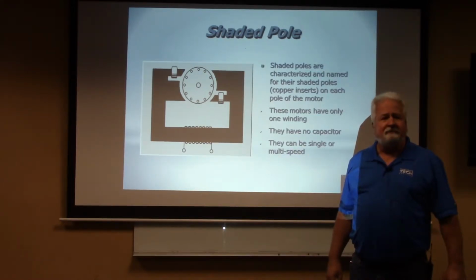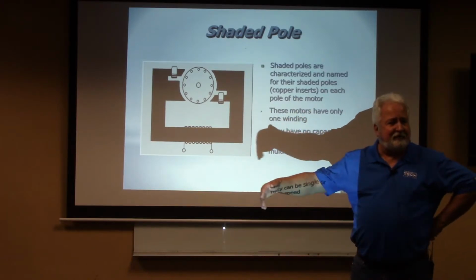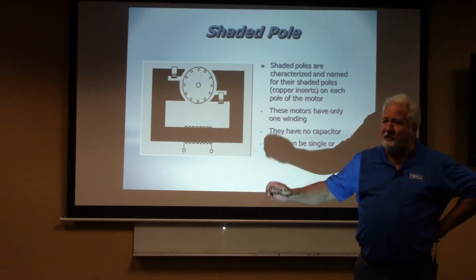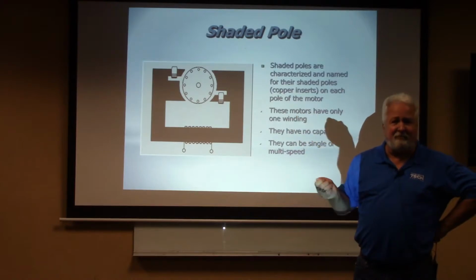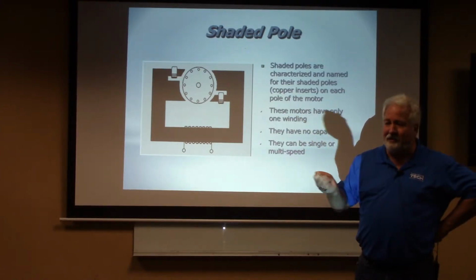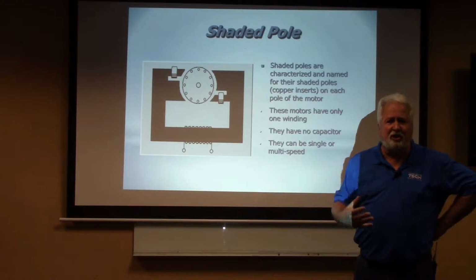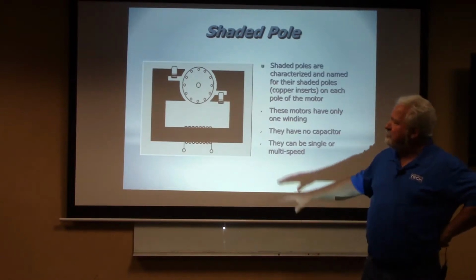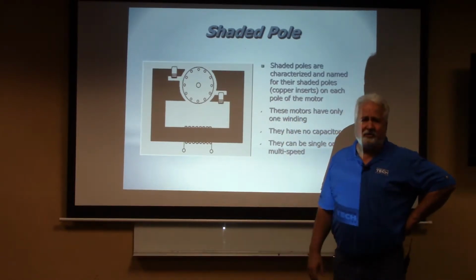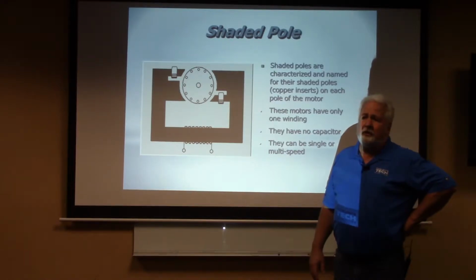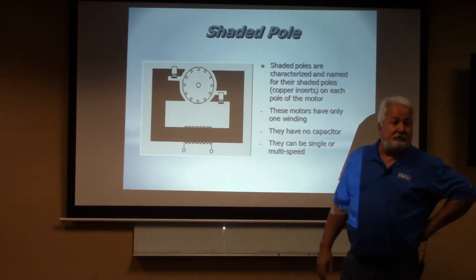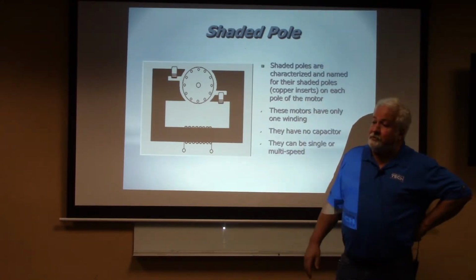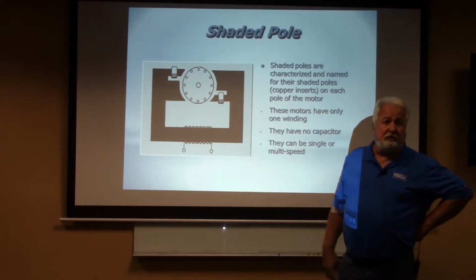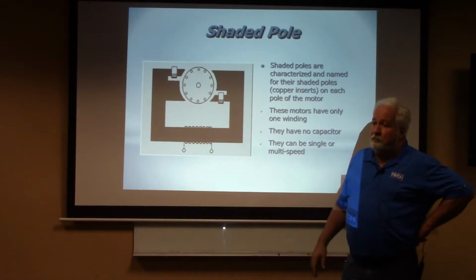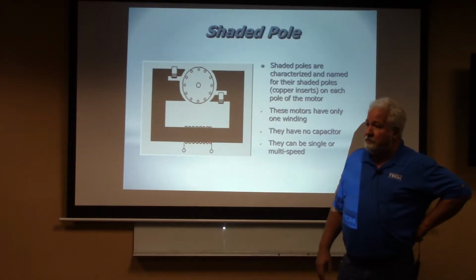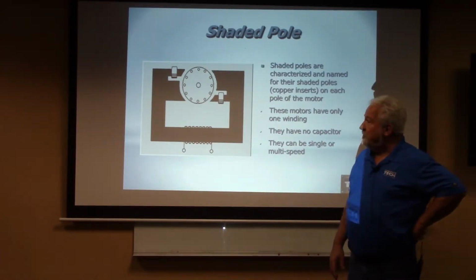You remember the fans that Grandma had next to her chair in the living room? She had that fan and you'd stick that pencil in there and stop the fan from going around. You guys remember that? Yeah, it kind of stopped. It didn't have a lot of starting torque. We could stop that. It was a shaded pole motor. There was no capacitor to it. This is what we're going to use on our inducer fan motors, attic ventilator motors. All of those are going to use some sort of a shaded pole motor. No capacitor to it, just voltage in, voltage out.